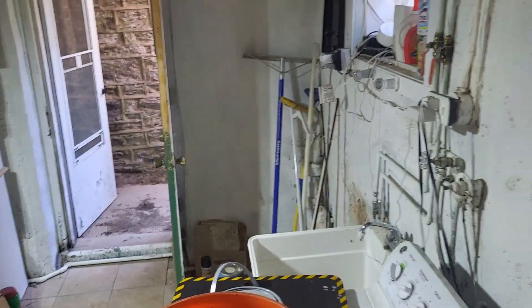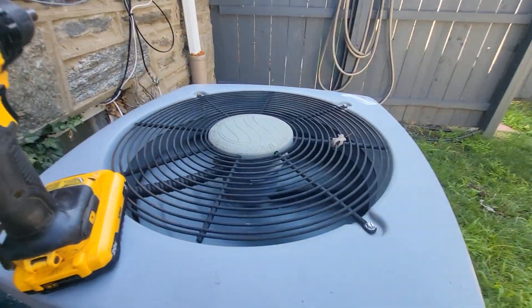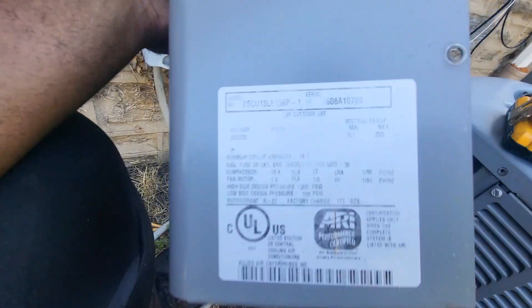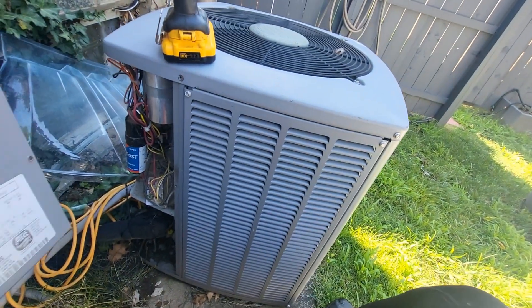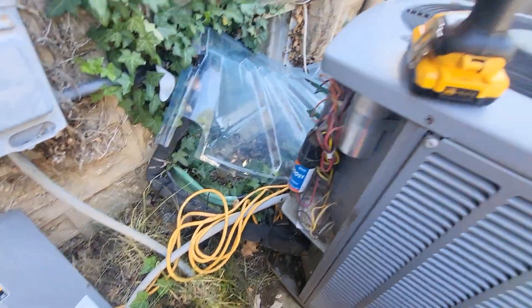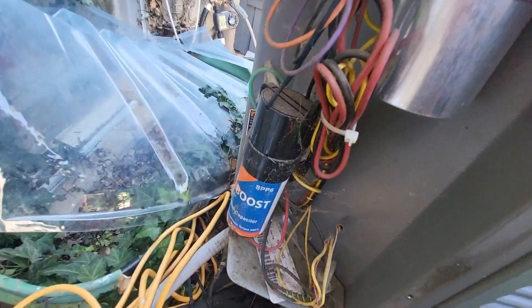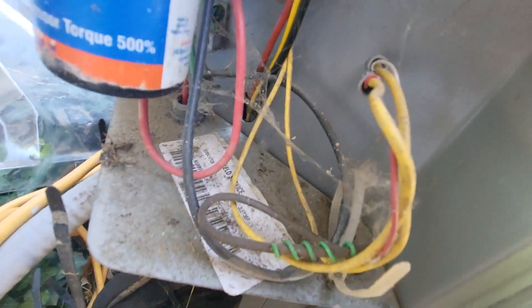Let's go outside and take a look at the outside unit. I'm going to check that for amps. This is a 13 SEER, 3-ton unit. This doesn't look like 2016 — this looks like 2008. It's an R22 unit, and it looks like we already got a hard start and cap replaced years prior.